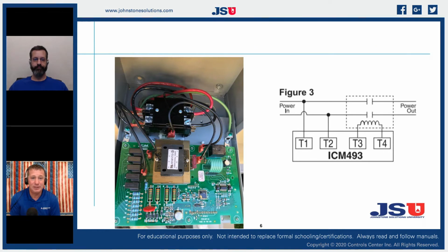They are, absolutely. It's funny that you say that, because that's actually where I was heading to. That is my favorite surge protector on the market, is the ICM 493. So that ICM 493 adds a variety of things to it. So it adds the surge protection, it adds the voltage conditioning, and now it's actually going to offer an isolated contactor for that power source. So not only is it protecting the equipment, it can completely isolate the piece of equipment in those conditions. And it just does a really good job of doing that. And it's a simple installation.